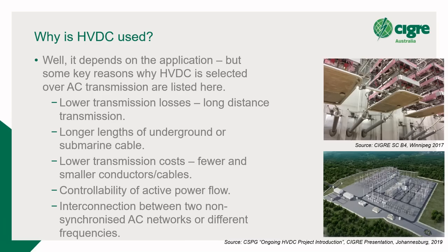And then the final one, which is not as relevant here, but it is a reason, connecting two non-synchronized AC networks. When we connect a direct link, there was no interconnection between Queensland and New South Wales, for example. So a DC connection allowed that connection. Another good example is Japan, where a significant amount of the country is in 50 hertz, and another part of the country is in 60 hertz. So they often use HVDC converters between the two networks as back-to-back converters to allow that connection.